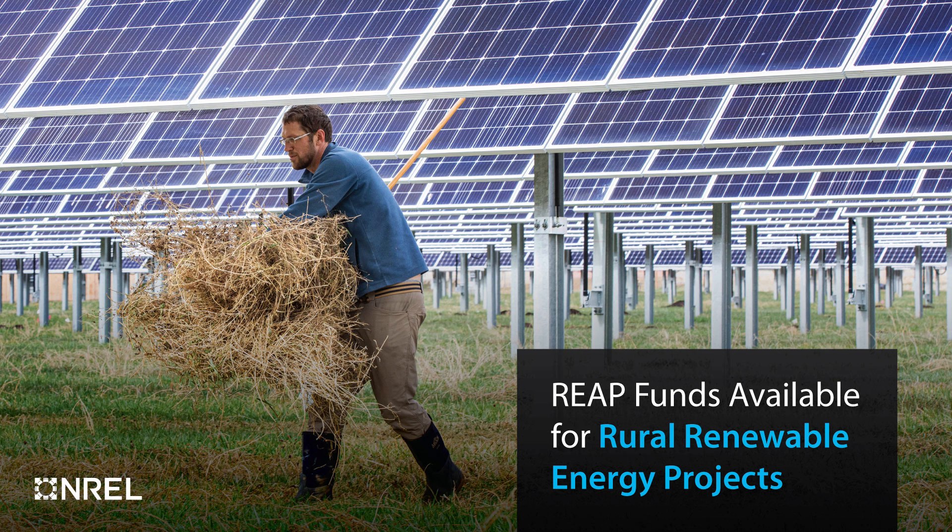Typically, the larger the load, the smaller the battery size relative to that load. For example, if you have a residential grid-connected system, you might go up to about a day's worth of autonomy. If you're talking about a large commercial system — say several hundred kilowatts or megawatt scale — it might be 1, 2, or 3 hours.